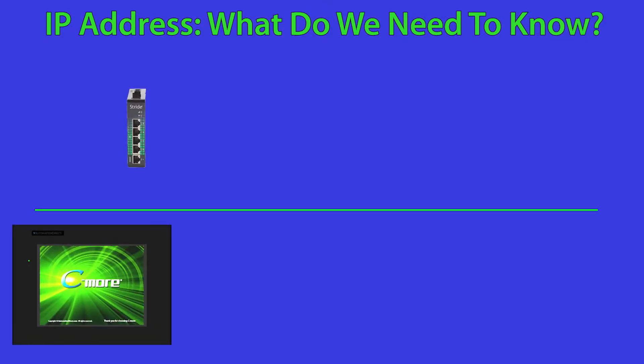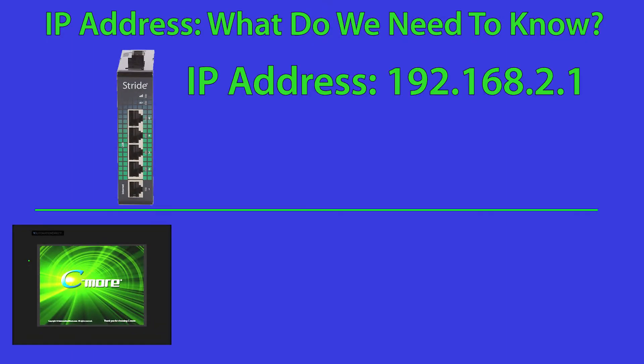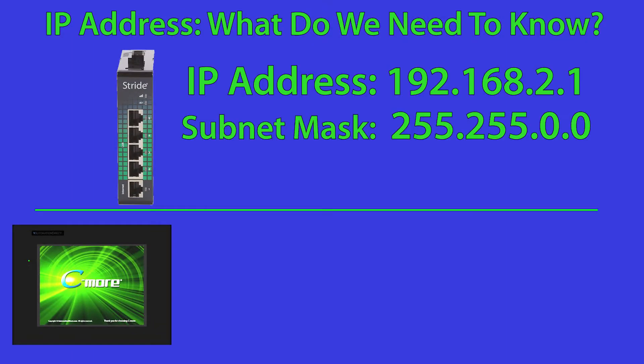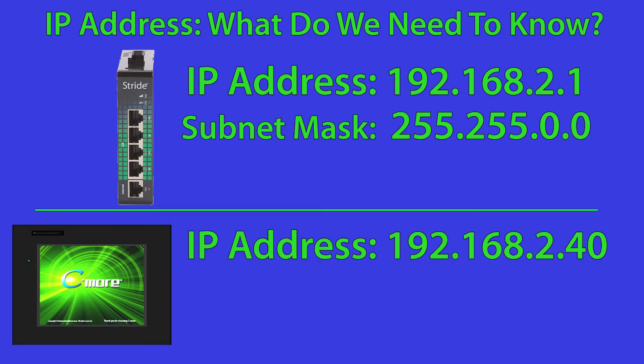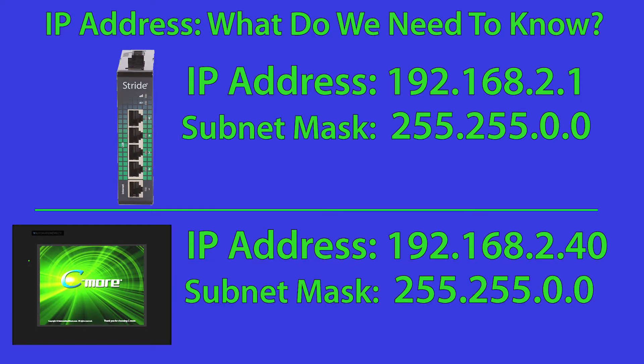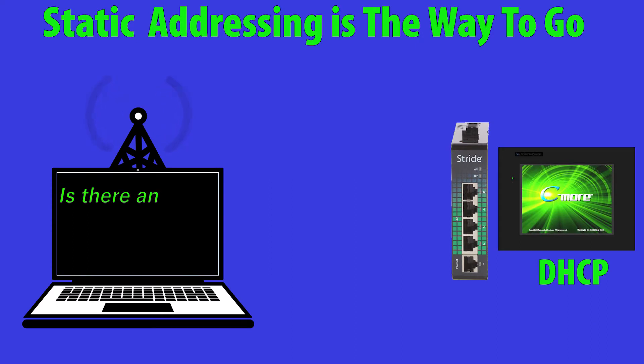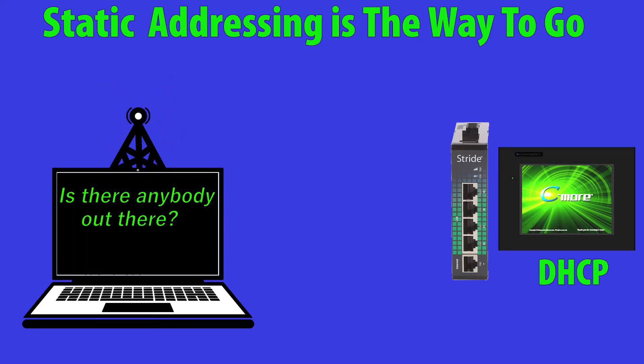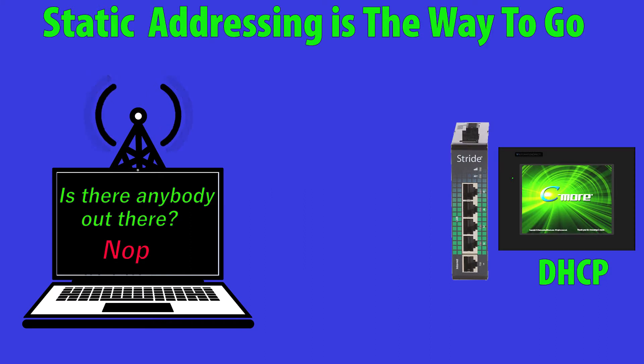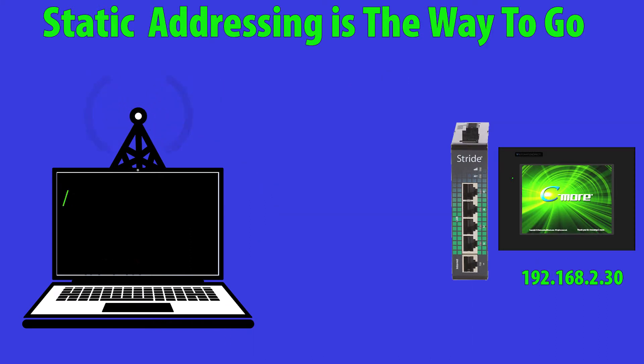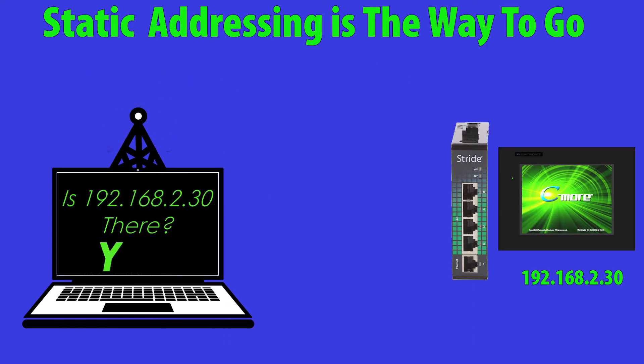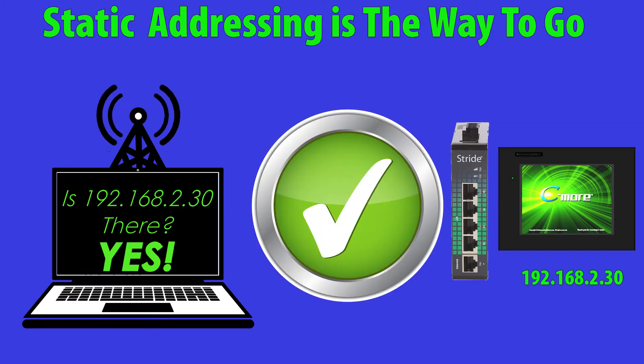First we need to discuss the C-more's IP address. In this example, this is the IP address of the VPN router on the control side. To remotely program your C-more HMI, it must be on the same subnet as the VPN router and have the IP address of the router as its default gateway. This way the C-more will be communicating through the router. It is very important that everything is a static IP address as one limitation of VPN networks is that broadcast comms will not work and broadcast comms is what is used for auto discovery of devices.